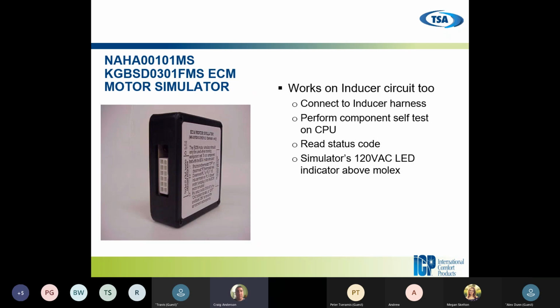This little device also works on the inducer. So when we're talking about a modulating furnace, this furnace has a modulating inducer. It is an ECM inducer, just like the fan motor. It's a little different in testing. If you don't have the testing procedures written down, then it's a hard guess which brown, yellow, or blue wire I need to test. This takes all the guessing out of the equation. It sends a good signal to your board, and we can move on just by plugging it in.